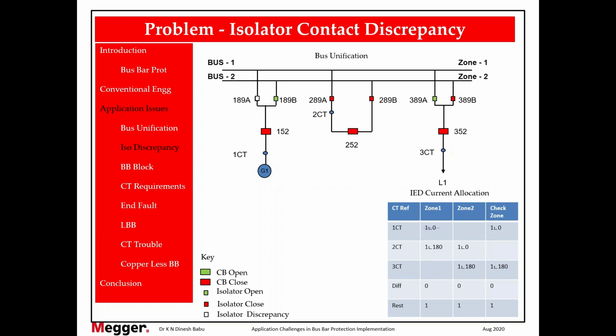Let us see. The moment this isolator status is missing, this current will vanish from zone 1. But the check zone will not eliminate the current because it is independent of the isolator status. So the main zone may pick up. So what will happen to this differential current? It will read current. And in a conventional system, we have taken a worst case scenario, with only 3 bays here. Normally you will have 10 bays, 15 bays, 20 bays, etc.